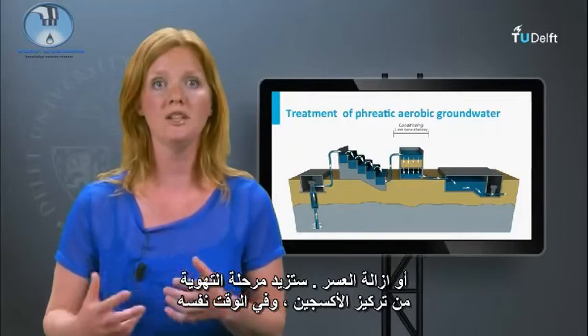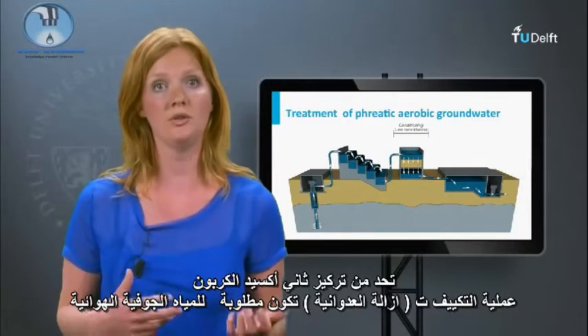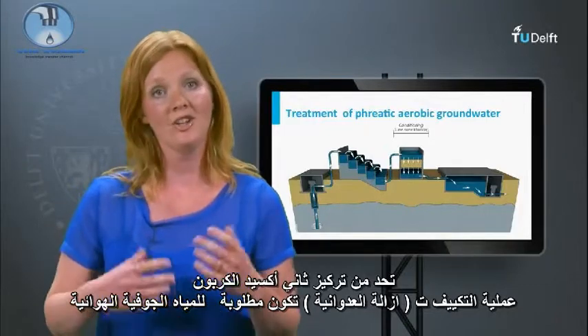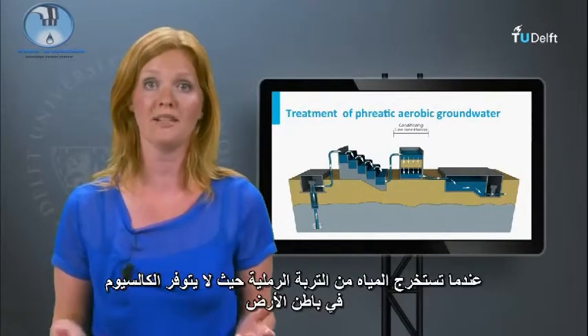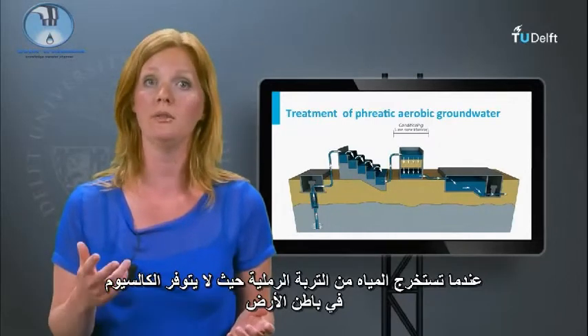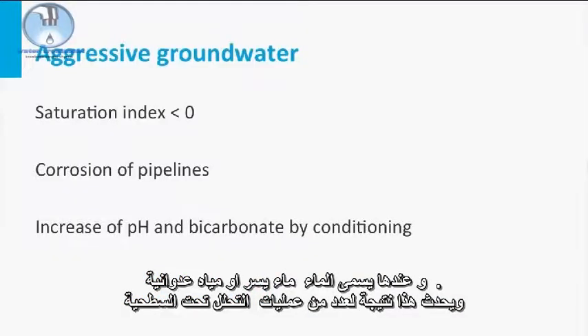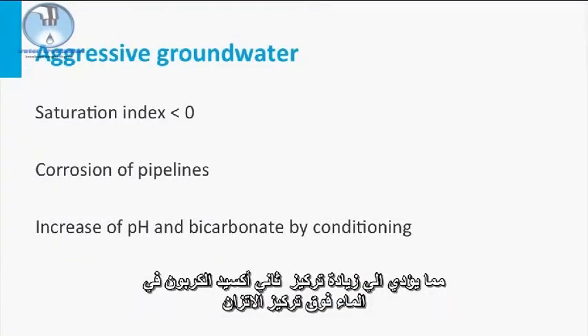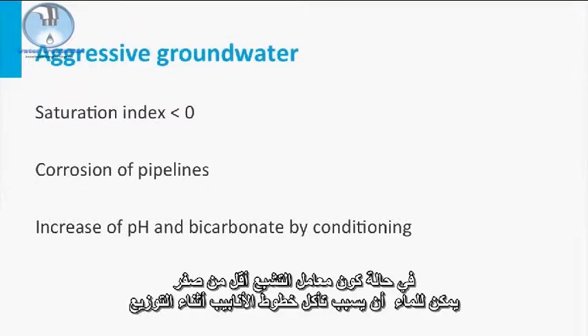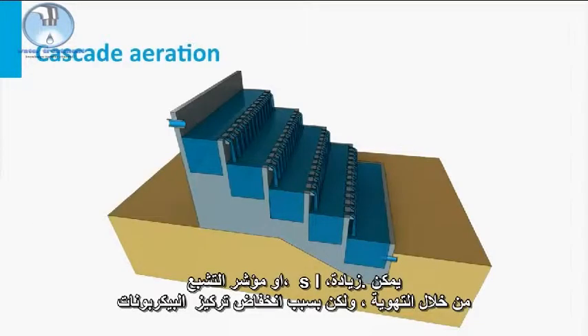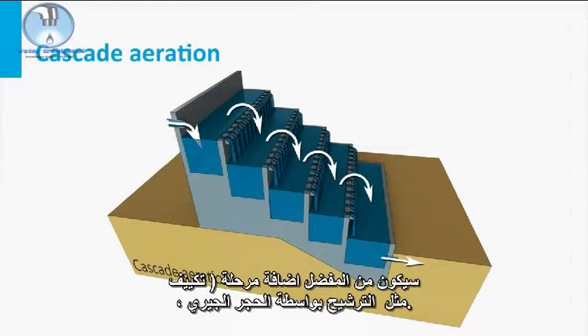The treatment scheme for aerobic groundwater is generally very simple and consists of aeration with optional subsequent conditioning or softening. The aeration phase will increase the oxygen concentration and at the same time reduce the carbon dioxide concentration. Conditioning is desired when aerobic groundwater is abstracted from sandy soils where no calcium is available, producing soft or aggressive water. The saturation index (SI) can be increased through aeration, but because of low bicarbonate concentrations, it may still be recommendable to apply a conditioning step such as limestone filtration.